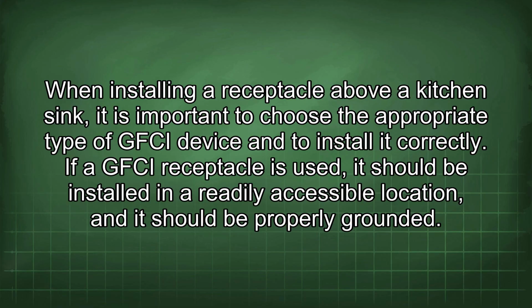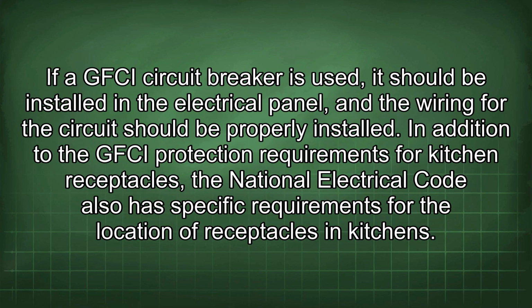If a GFCI receptacle is used, it should be installed in a readily accessible location and it should be properly grounded. If a GFCI circuit breaker is used, it should be installed in the electrical panel and the wiring for the circuit should be properly installed.